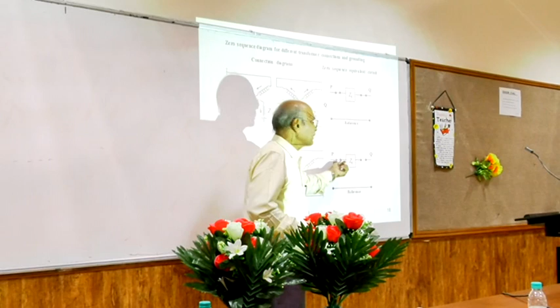And how about the impedances? How do I take care of them? What is Z0? It is the zero sequence impedance of the transformer plus 3 times this one plus 3 times this one. That must be equal to Z0. The transformer will have its own zero sequence impedance, and there are two grounding impedances which I should multiply by 3 and then add. Now I think I can explain this.